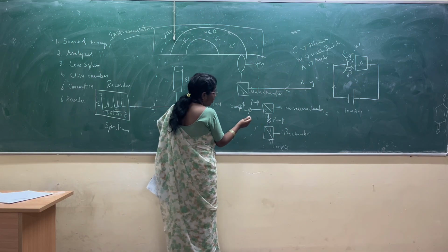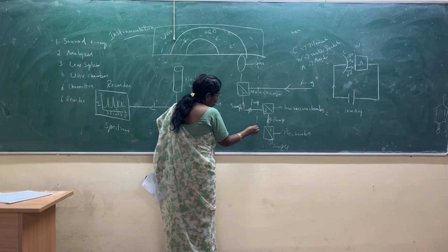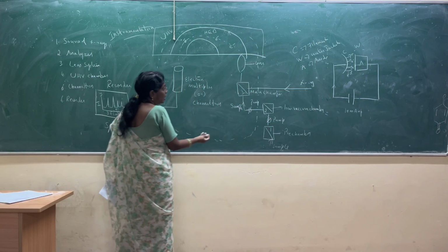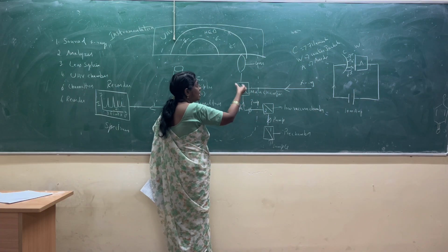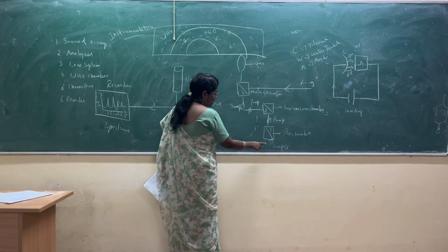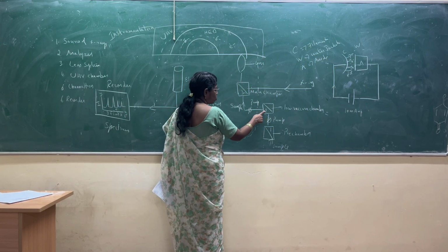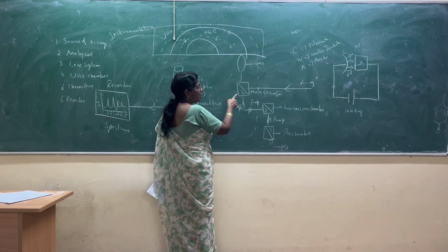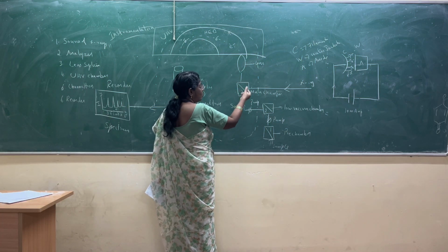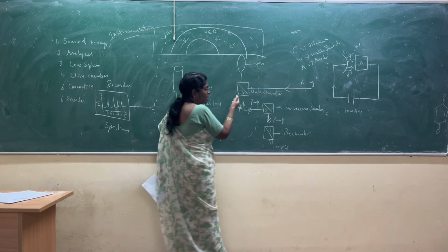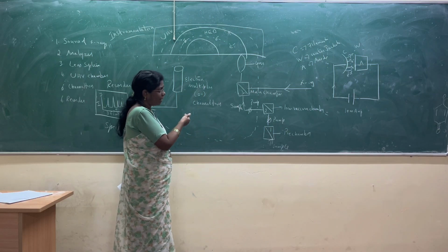So the main chamber alone is inside the ultra high vacuum. For the pre-chamber and low vacuum chamber, see here, I put a dotted line, so only a vacuum environment is maintained there. The sample is introduced into the pre-chamber, pumped into the low vacuum chamber, and pumped into the main chamber. The main chamber is inside the vacuum environment, and the X-ray source irradiates the main chamber.